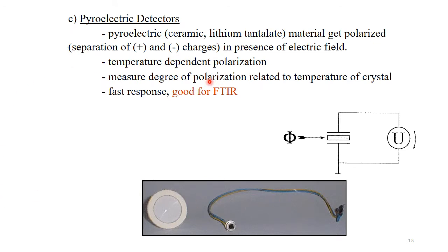Pyroelectric detectors. Pyroelectric ceramic, such as lithium tantalate material, gets polarized, with separation of positive and negative charges in the presence of an electric field. Temperature dependent polarization: measure the degree of polarization, which is related to the temperature of the crystal. Fast response, and it is good for Fourier transform infrared spectroscopy, which is also known as FTIR.